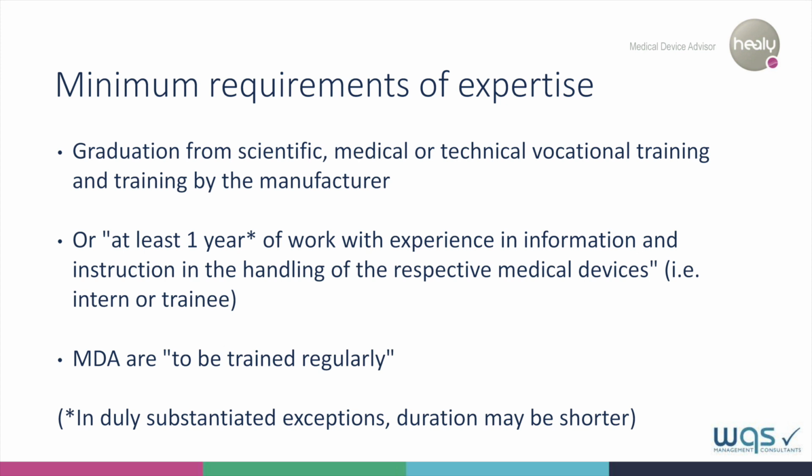Paragraph 31 of the German Medical Devices Act states that expertise only exists if the following conditions are met. The MDA has successfully completed training in a scientific, medical, or technical profession and has been trained in the relevant medical devices. Or the MDA has gained experience with and information about the respective medical devices and, if necessary, the instruction regarding those devices through at least 1 year of professional activity. This time period may be shorter in some justified cases. MDAs must be trained regularly.